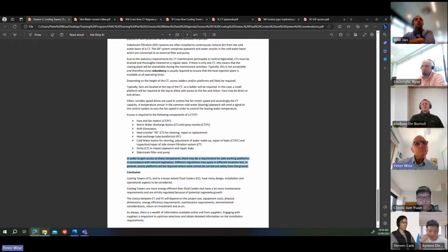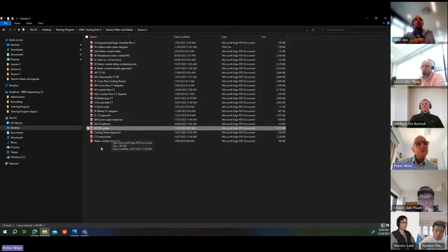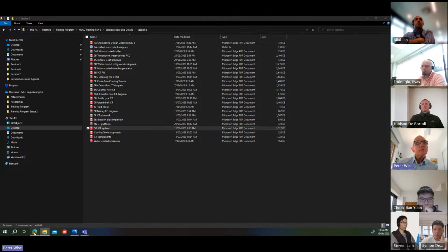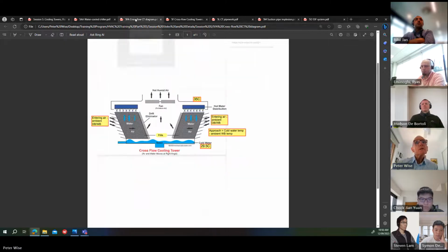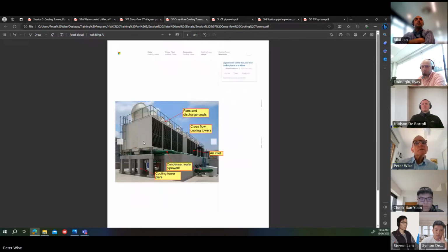Okay, so some of the drawings, some of the pictures we've already seen. This one, you can see there's an access ladder up the side. There's a platform on the top, so you can get to the water distribution basins. You can get to the fans. Also, for a cross-flow cooling tower with this access door, there's usually a ladder inside, so you can climb up inside. You can clean the fill. You can take the fill out. I'll show you another picture.